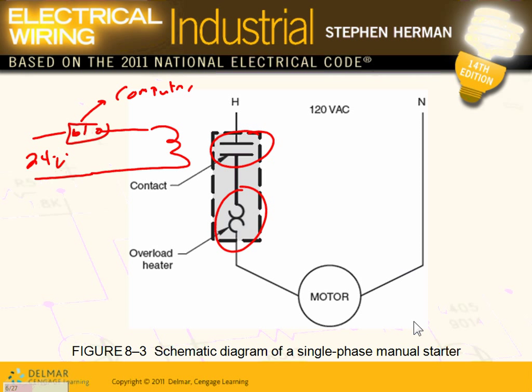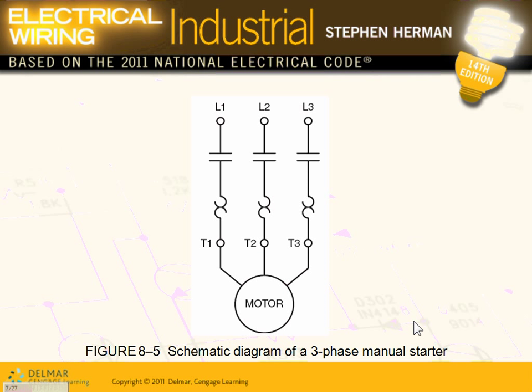Contactor plus overload makes a so-called motor starter, also called a magnetic starter. A manual starter means you have to flip it by hand. A magnetic starter has a little coil. With three-phase motors, if it says manual, there's a switch you physically, mechanically close to make those contacts. There is no coil whatsoever in a manual starter.